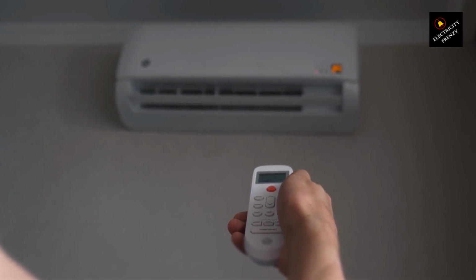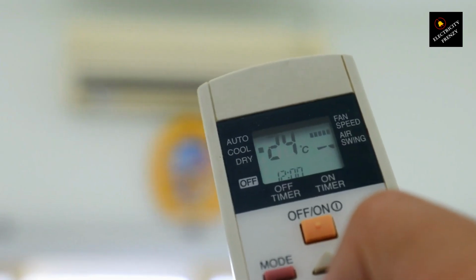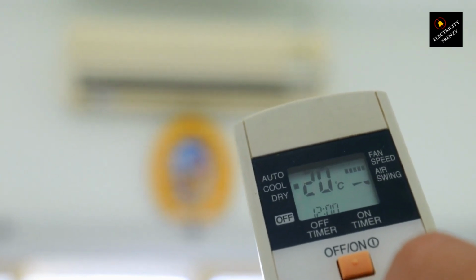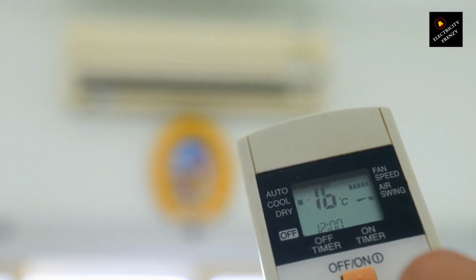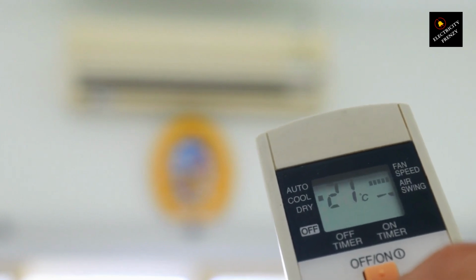Solution: to solve an overload issue, you have a few options. First, ensure that the air conditioner is the only major appliance connected to the circuit. If other appliances share the same circuit, redistribute the loads to different circuits. You can also upgrade the circuit breaker to a higher amperage rating if the wiring supports it. If the overload persists, it's recommended to consult a professional for further inspection.